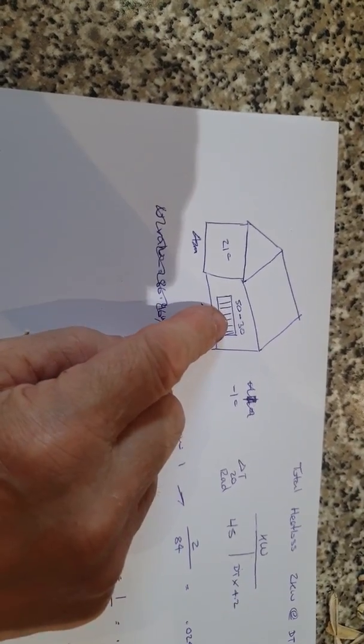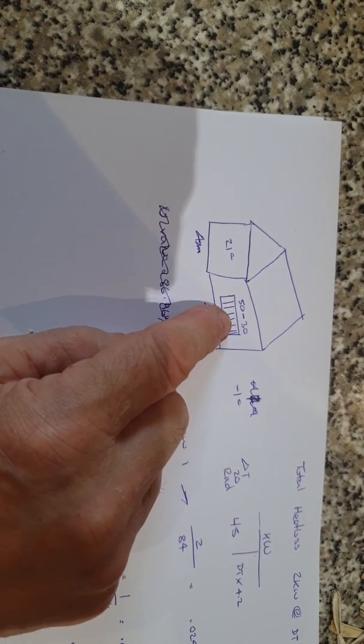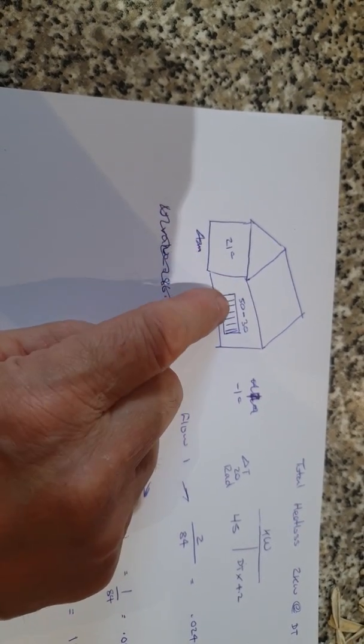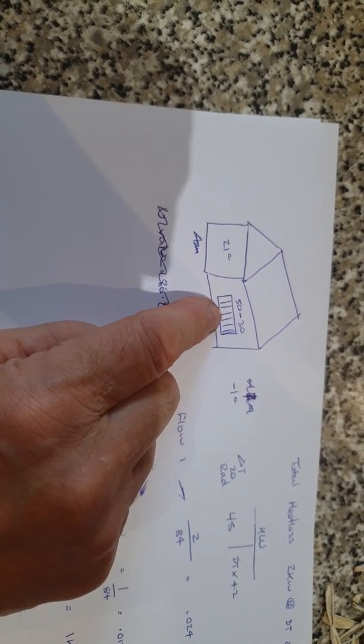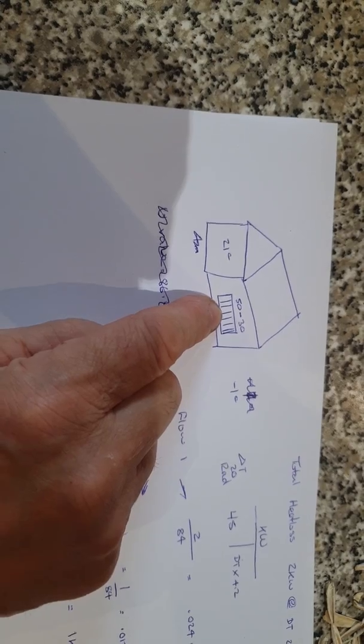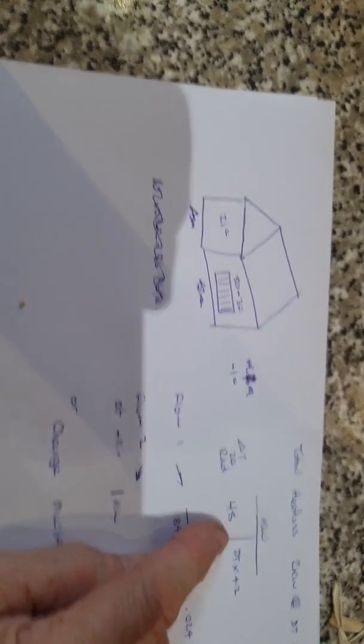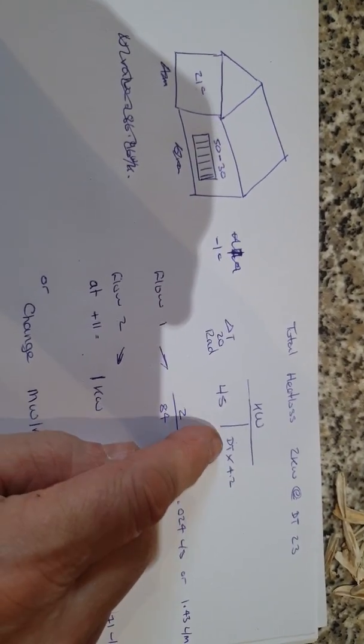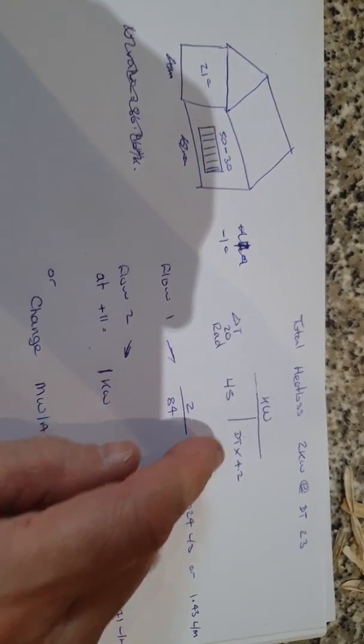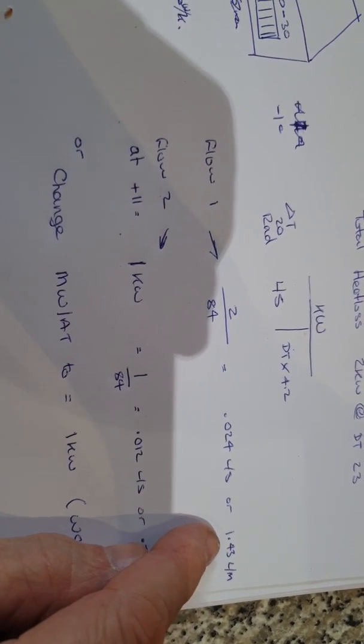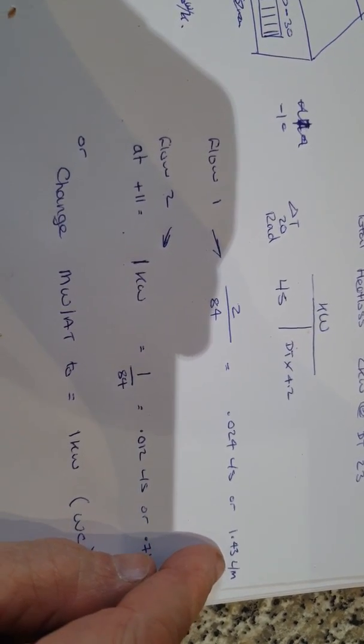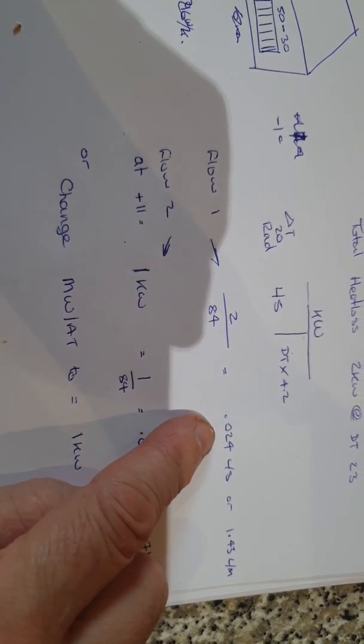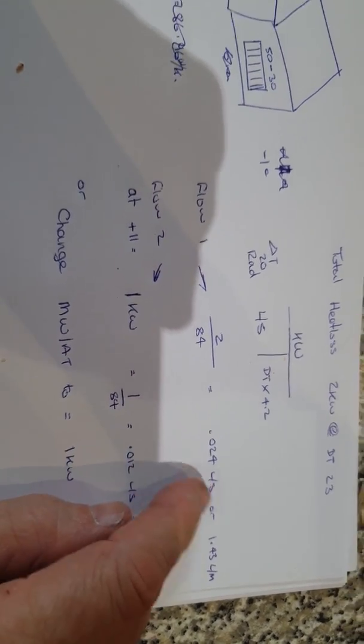At that point, if it's minus 1 outside, we will have a heat loss of 2 kilowatts when it's 21 inside. If we've got 40 degree mean water temperature here, we will have a flow rate according to our mass flow rate calculation of 1.43 litres a minute or 0.024 litres per second.